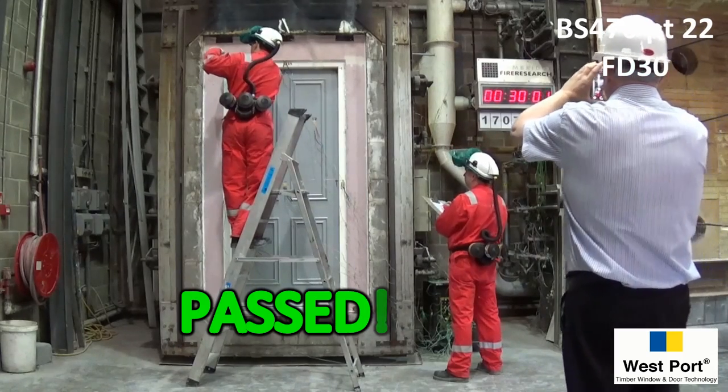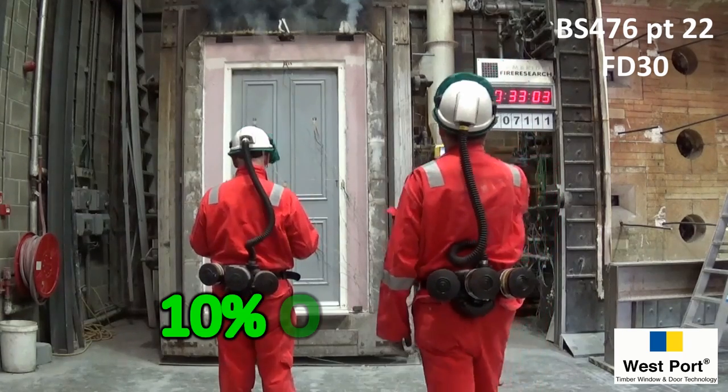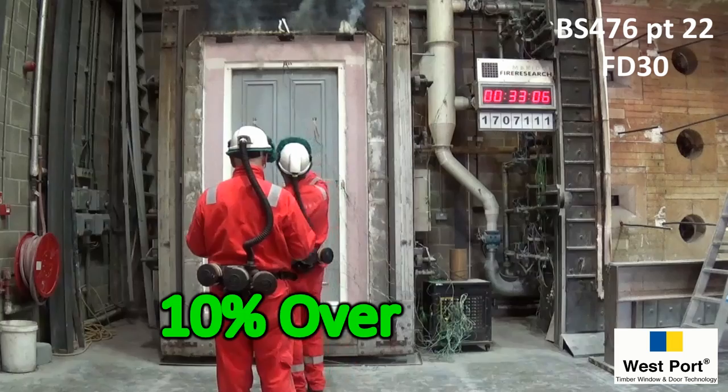At 30 minutes, the door has passed the test but continues on, holding the flames back well over 10% longer than the British standard requires.